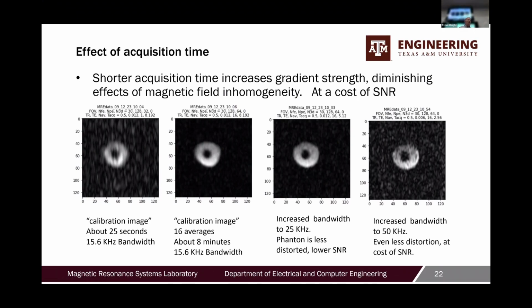That's the magnetic field image you should deal with. How do you solve that? You increase your gradient strength, so it dominates the magnetic field variation. And okay, we increase the gradient strength to increase our bandwidth to 25 kilohertz. We get a much more round image, but the signal to noise went down. If you go up to 50 kilohertz, it's a bit more round, but you've lost more signal to noise. So you have to find your optimum. It's a trade-off. Everything's a trade-off in MRI.